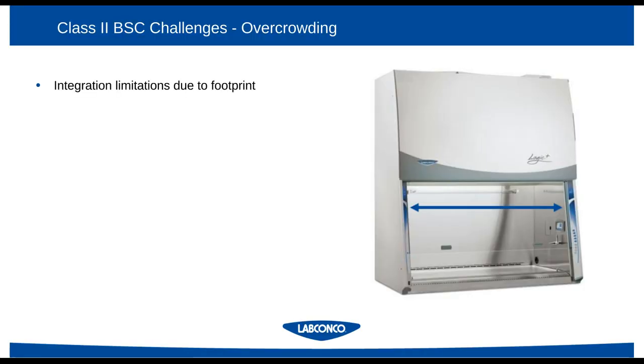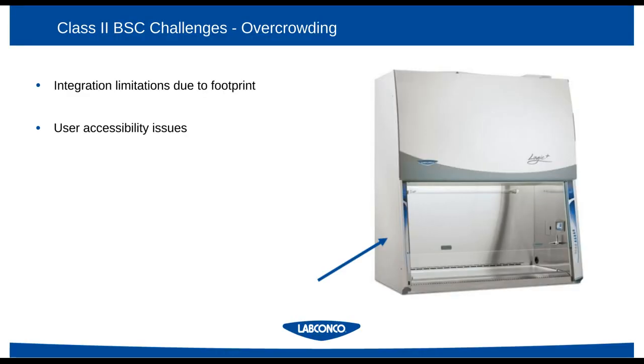Additionally, when you're incorporating those instruments into biosafety enclosures of all types, it's important just to look at the footprint of the enclosure. Also look at the user accessibility issues. As I mentioned, on a typical biosafety cabinet, you have left, right, and rear walls that are all stainless steel construction with limited ability to access instruments from the back and sides.